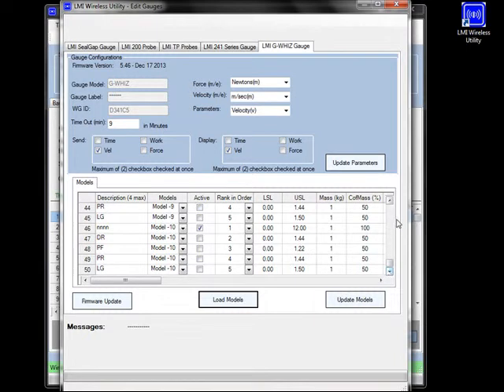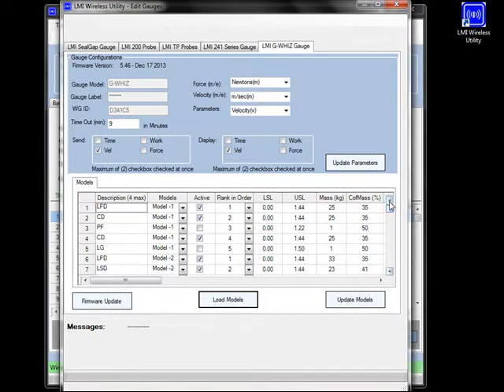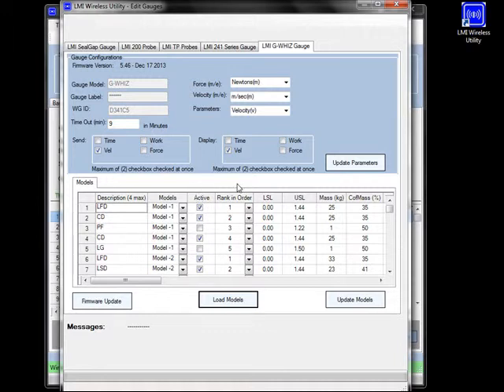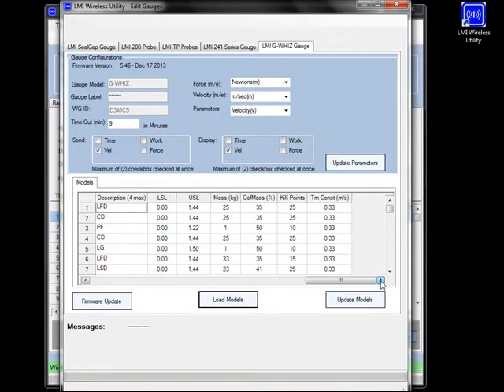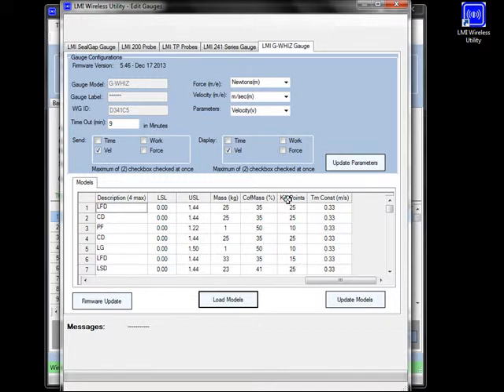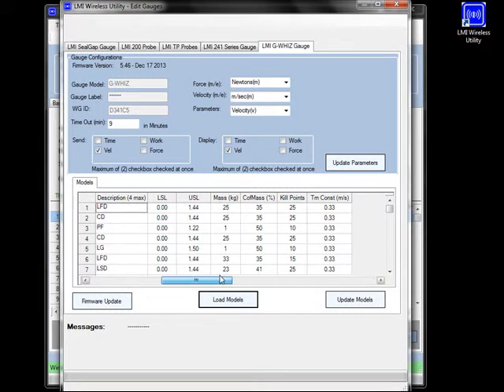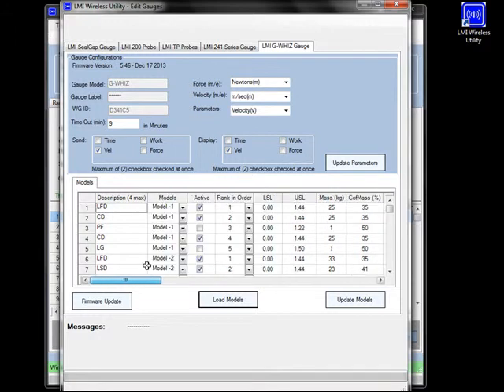You'll notice in the description column over here that you are able to have a four-character maximum name for each different door. You can select what model that door appears in, whether or not it is active or inactive in the part file, what order you will take the measurement in. You have your lower specs and your upper specs. These are what determine whether a door is considered good or bad. And then to the right of that we have mass, center of mass, and if we can scroll a little bit further, we will see kill points and time constant. Now these last four columns are used for force and work measurements. So if you're going to be using those, be sure to consult the manual as it goes into a lot greater detail about what each one of those entails.